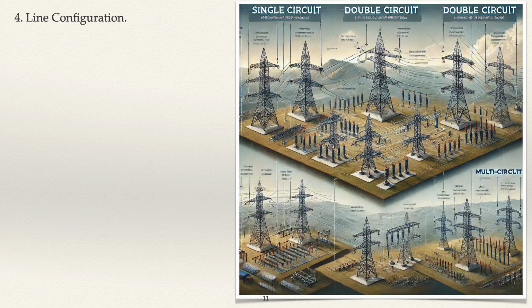Line configuration matters because an optimized configuration reduces power losses and improves reliability. It ensures compliance with clearance and insulation requirements to prevent accidents. A proper configuration minimizes land usage and reduces construction costs while maintaining performance. It provides flexibility for future capacity upgrades or operational changes. The design criteria for line configuration determine how conductors are arranged to achieve the desired electrical, mechanical, and safety performance. By selecting an appropriate line configuration, engineers ensure the transmission line meets the required operational and regulatory standards.